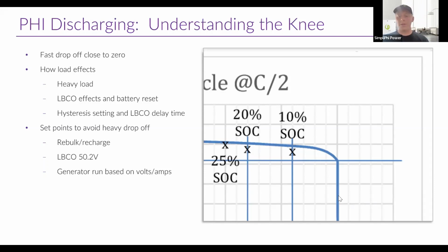One way to avoid this issue is by setting your low battery cutout to 50.2 volts. If you're not able to do that, you can set your generator to auto start when your battery reaches 50.2 volts and set your low battery cutout as low as 48 volts. 48 volts is really the absolute minimum low battery cutout that I would recommend for our batteries. If you're going below that, there's a very good chance that you could damage those cells, especially if it's a repeated event.